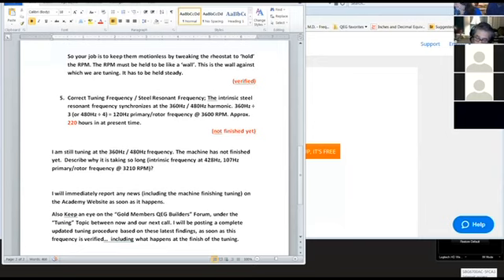I did a careful analysis yesterday, and the other frequency is actually 428 hertz. So it's 107 hertz on the primary at 3210 RPM. Right now we're running at 3600 RPM for the 120 hertz frequency. But when I'm running at 120 hertz, you can hear both of these frequencies. I can hear the 480 and the 428, and actually there you can hear them. What's happening, and this is the reason I think it's taking so long, is that it has to push that other frequency out before it can embed itself.